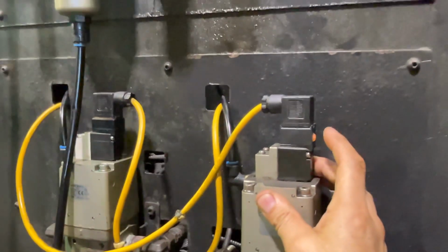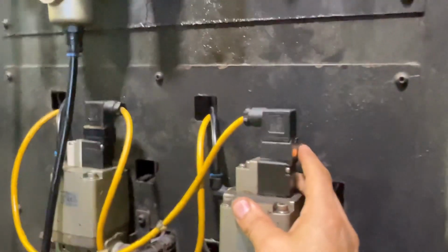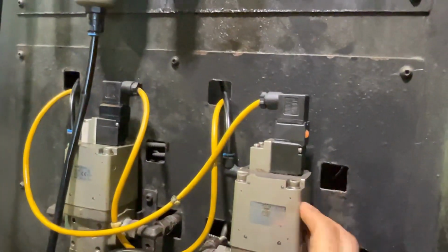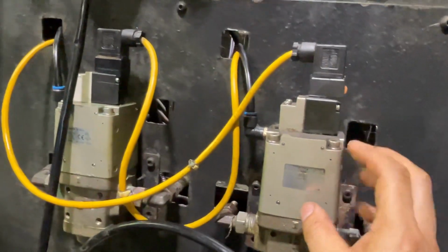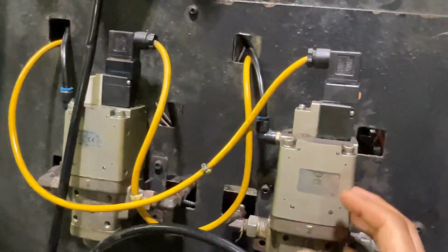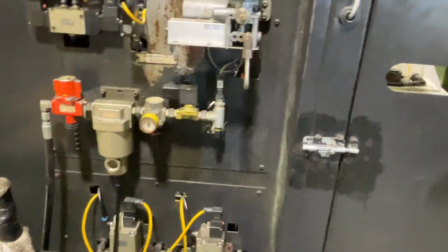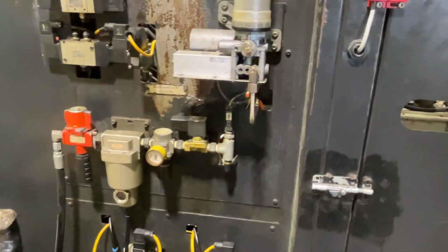If we don't have that, and we have the output on the PLC on, we can check the electrical part first, but most probably it's going to be the mechanical part, because this valve needs to be maintained periodically, cleaned and greased, and the O-rings replaced. Most probably it's going to be as we had today: the valve that you need to replace.